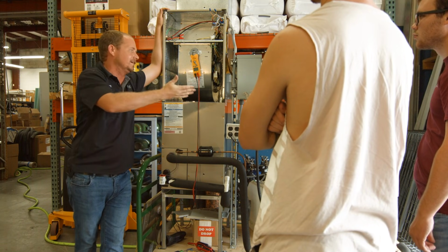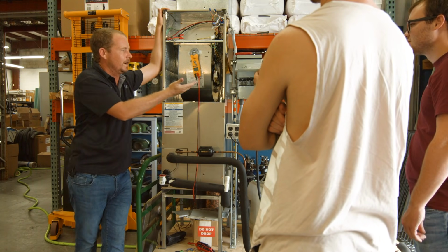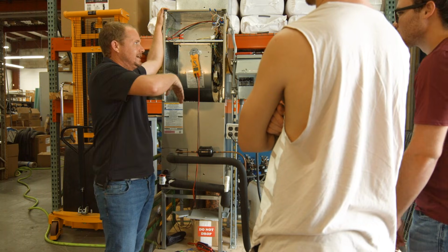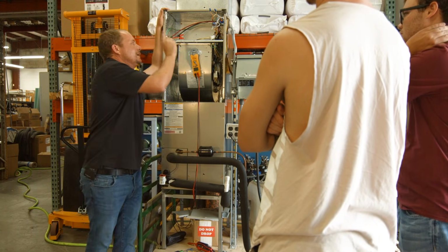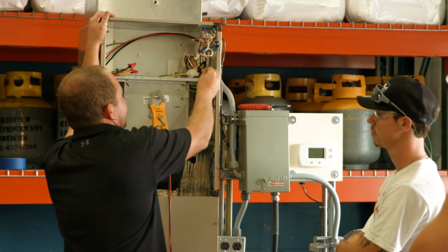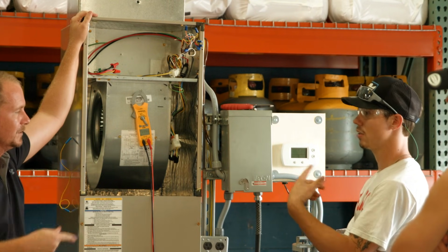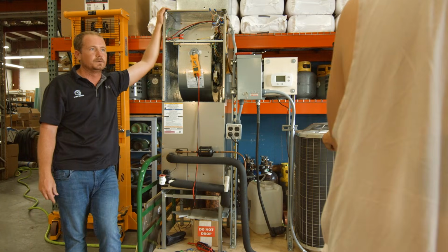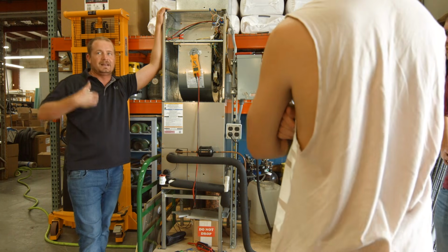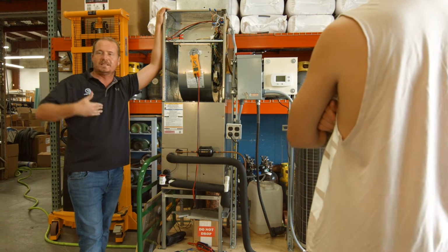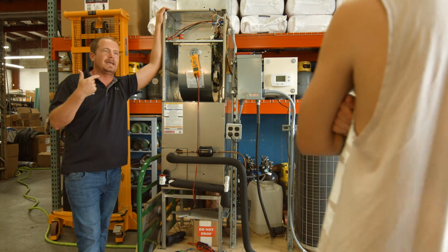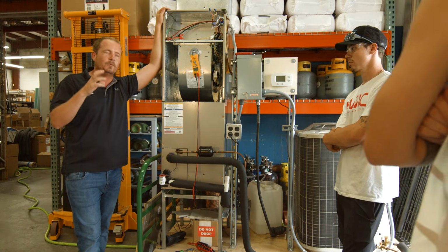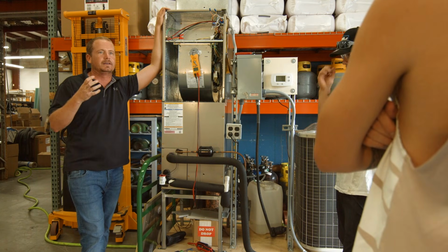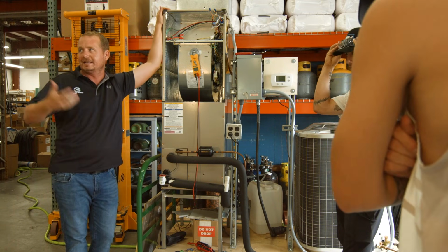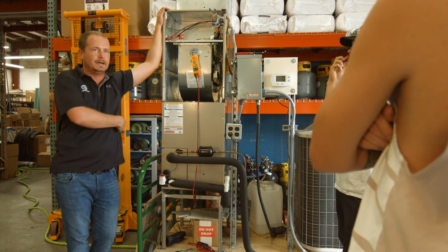Because I'm trying to take a shortcut here, in order for this to work properly, we still have to disconnect everything. But something interesting is happening here. This finally tripped, but you saw it tried to run a couple times. The thermostat has an overload protector in it, so when it sees too much current, it actually starts resetting. That's an issue we had with a couple models of thermostats where it made it hard to diagnose short circuits because it would just sit there and stay in time delay forever. It would never come out of time delay.